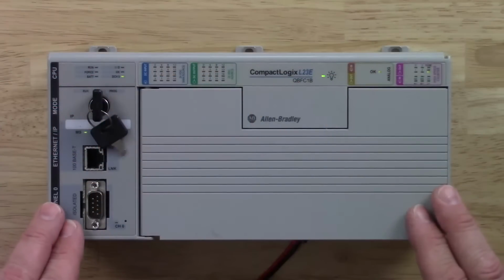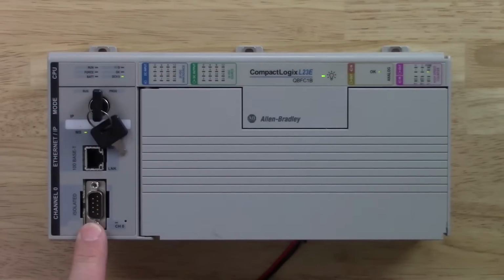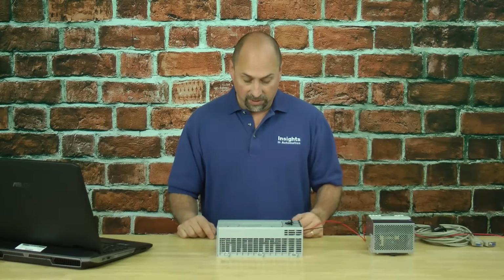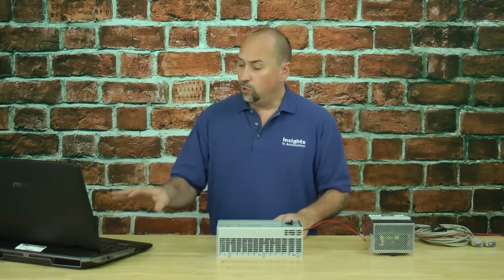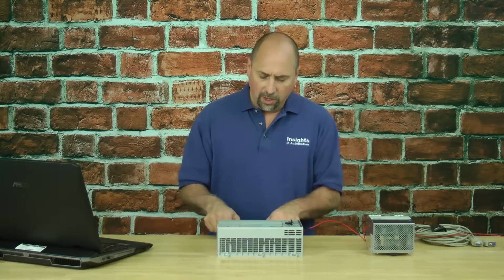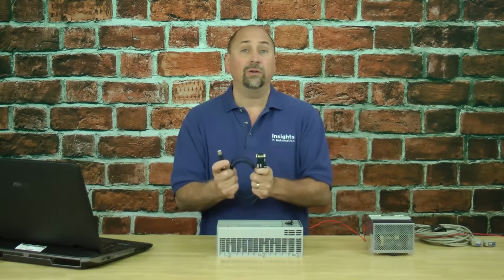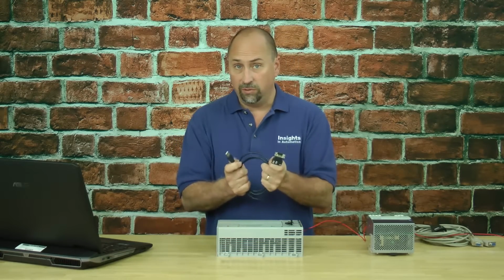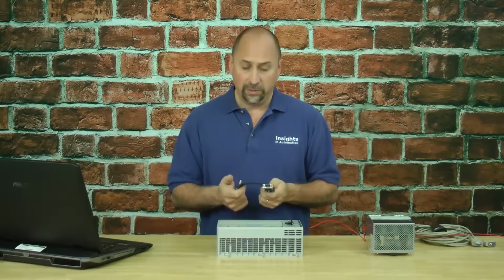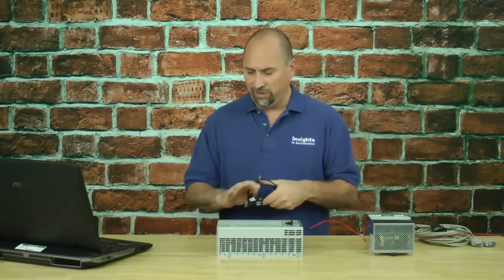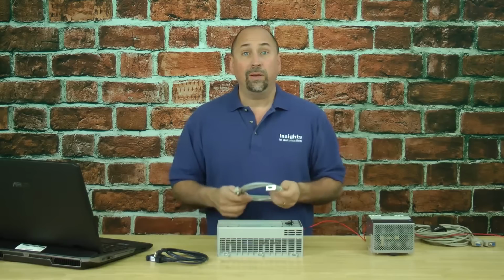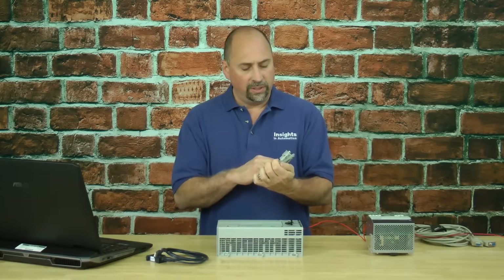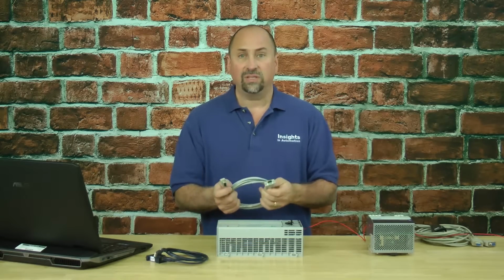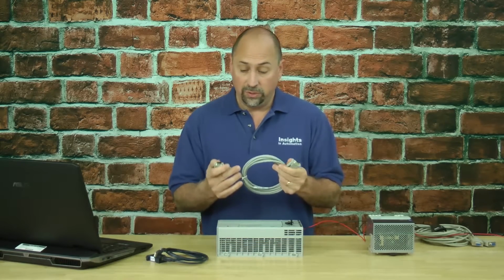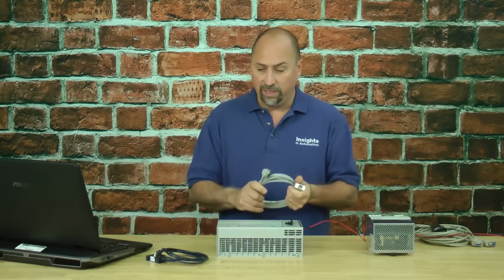Okay, here I have a CompactLogix L23 with a serial port, and I'm going to show you how to set that up today. Now, if you're like me, your laptop probably doesn't have an old-fashioned serial port on it. So, you could use the 9300 USBS, which is a USB to serial converter. It works very well. It's a great unit. It's kind of expensive. And then you'd probably pair that up with a 1747 or a 1756 CP3 cable, which is a null modem cable, 9-pin to 9-pin.